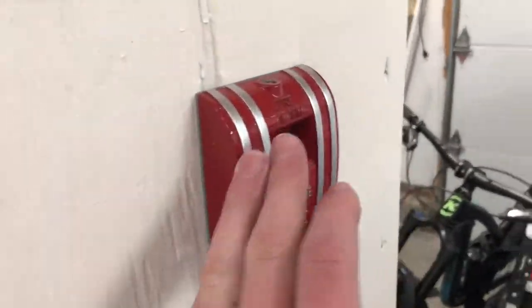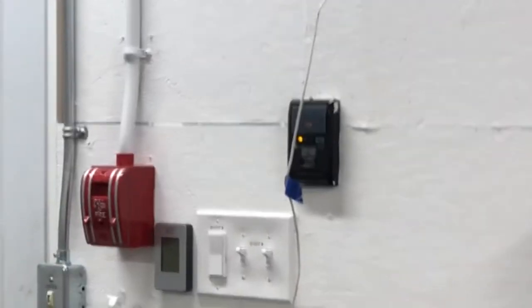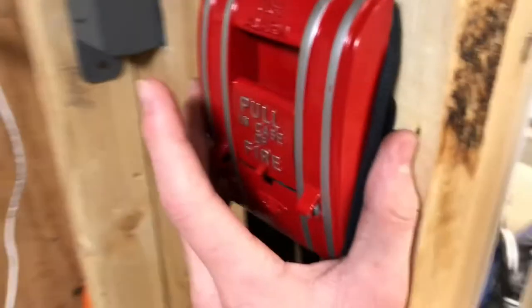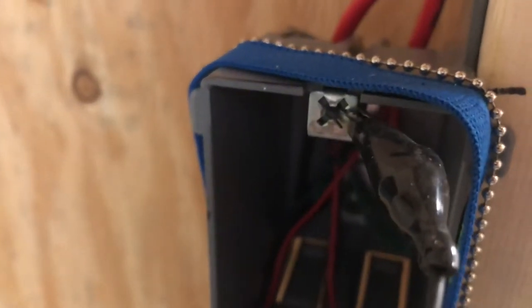I'm going to choose a pull station. This is our end-of-line device. This is our first device, so I'm going to pick somewhere in the middle. Let's do this guy right here. I've just created a negative ground fault. I've gone from our negative terminal on this pull station to our grounded box right there.